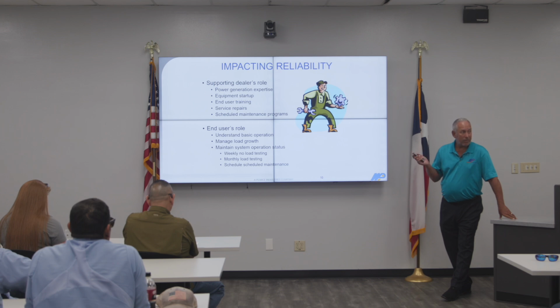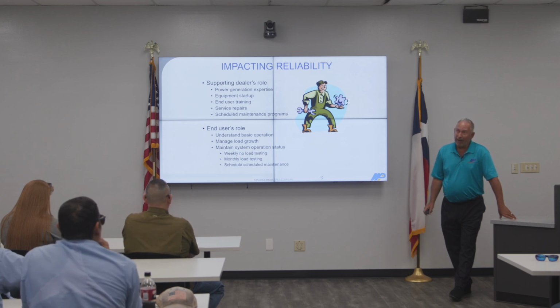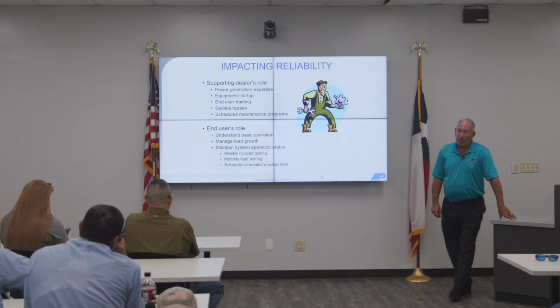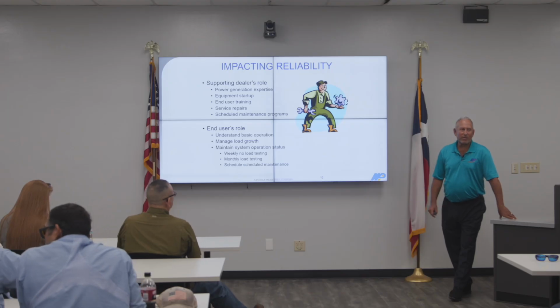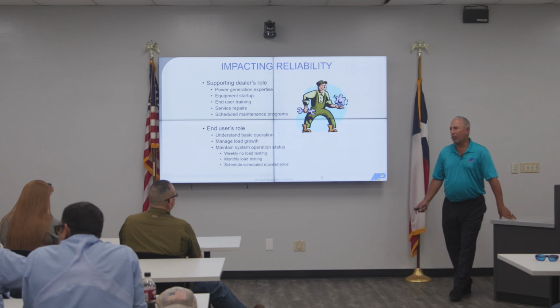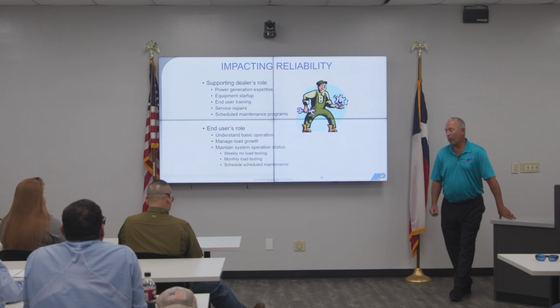Monthly load testing - I heard weekly load testing. We recommend weekly. I'll get more into this in the presentation, but running that generator is really important. To me personally - I started off as a military guy, a field service technician - running a generator without load on it is a waste of everybody's time and fuel, because the only thing you're testing are the start batteries. You're not rolling the building, not putting any load on it, it's just the start batteries. All you're proving is that at that point those batteries were good - that might not be the same conversation a week later. So putting load onto a generator is really important, and we'll go more into why that is.